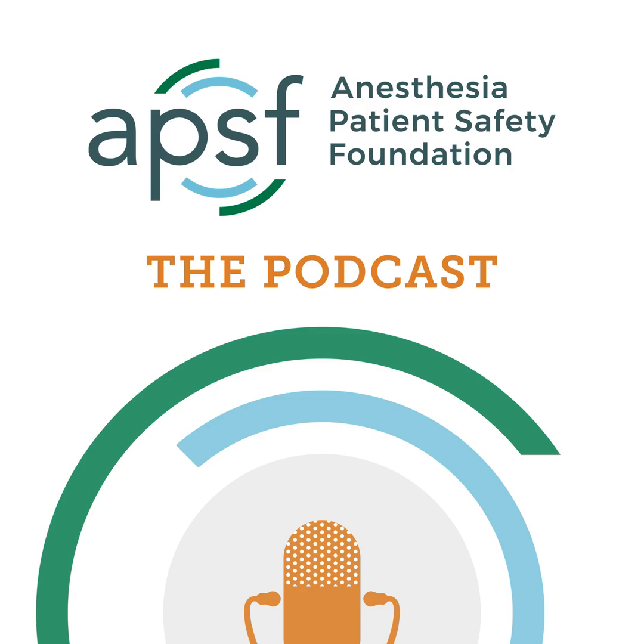Question 1. Please educate on the need for multiple filter use for each patient. Is it necessary to have both heat and moisture exchange filters and expiratory filters for all patients? If a site decides to use just one filter, which filter is the preferred filter for adult and pediatric populations? The short answer is that APSF recommends that a pleated filter be placed between the expiratory limb and the anesthesia machine. A high-quality filter in that location should prevent respiratory pathogens from entering the anesthesia machine.